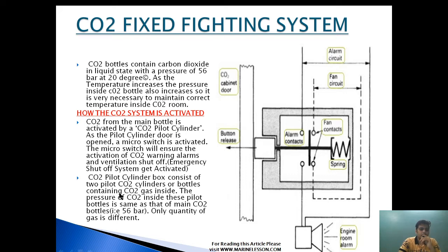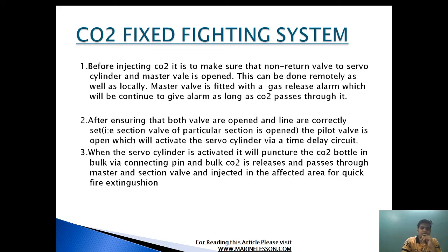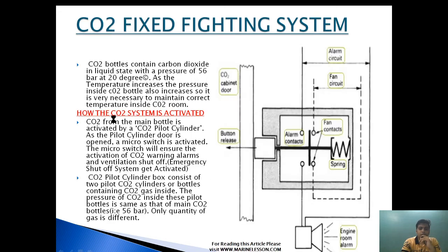The exhaust fan will go off to ensure good smothering action can be achieved. The CO2 pilot cylinder consists of two pilot cylinders or bottles containing CO2 gas, with the pressure inside the same as the main CO2 bottles — 56 bar — only the quantity of gas is different. Before injecting CO2, it must be ensured that the non-return valve to the servo cylinder and the master valve are open; this can be done remotely as well as locally.